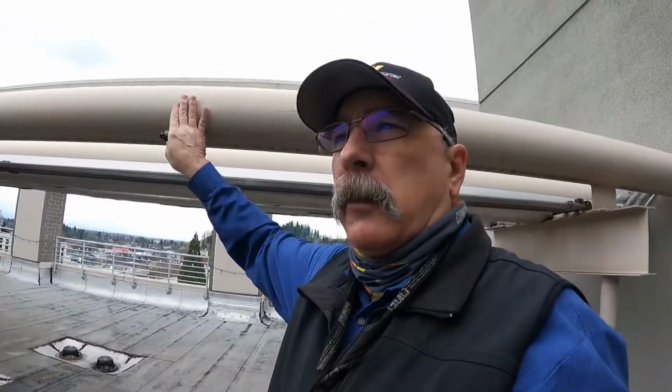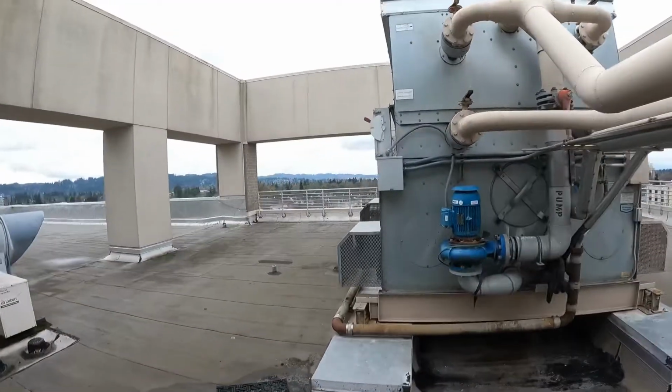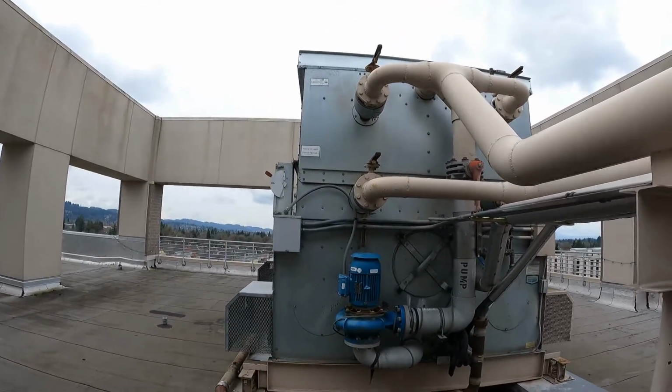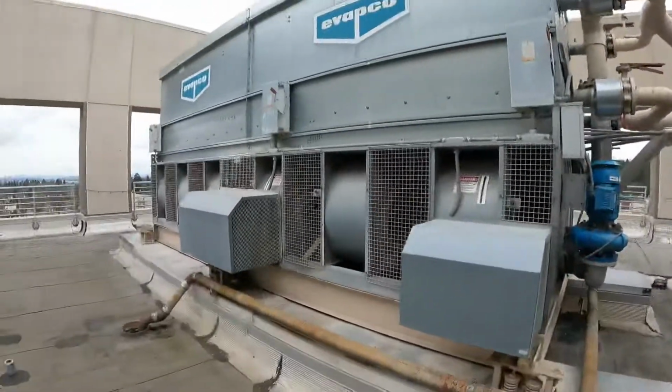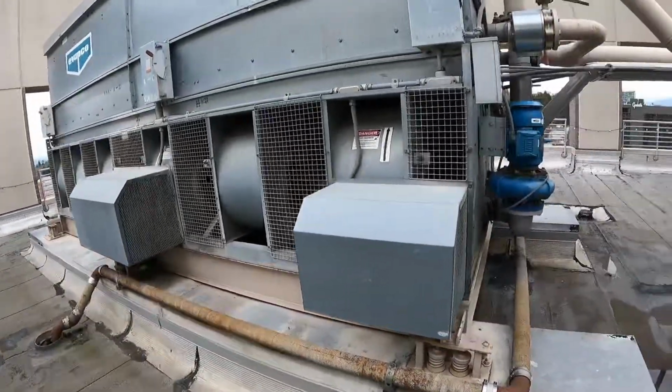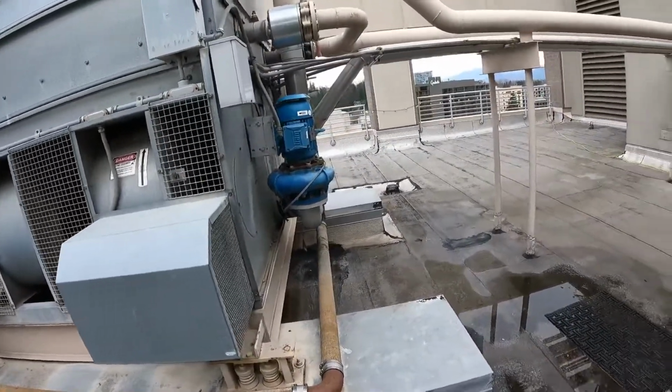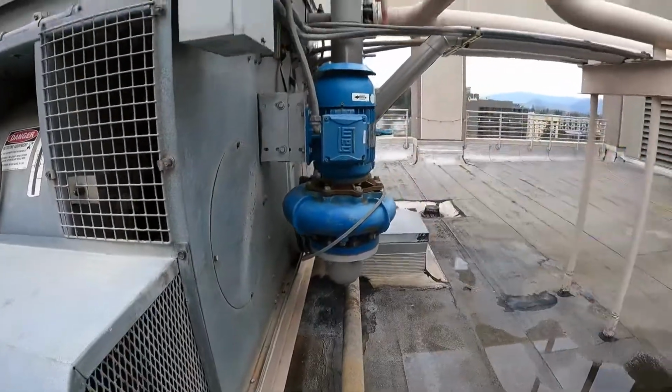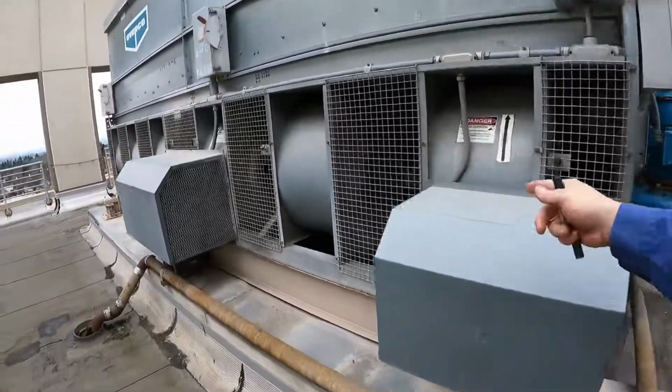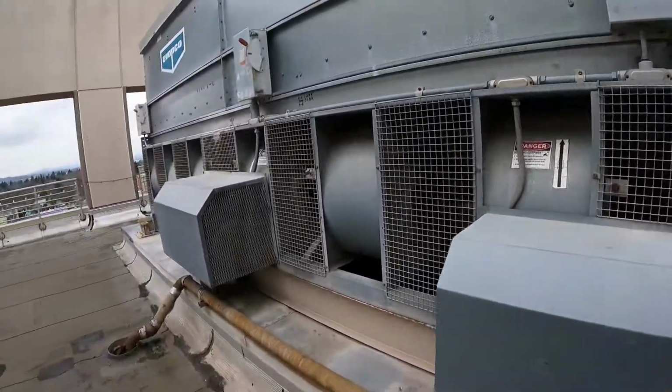Our warm water's coming in this pipe. It's going up there to a cooling tower up on the top, and we are passing it through another radiator, and then at that time we can either take that heat off by turning some fans on, pulling the air off or the heat off that way, or we can combine that with this pump right here that's actually going to circulate water that's internal to this machine, not related to our other loop, through a spray bar, spraying down over the top of our radiator and removing the heat from the water that way, so that now that water returning is cooler and can absorb some more heat that the refrigerant's going to give up to us.